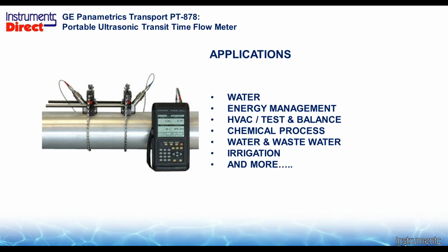Well, an ultrasonic transit time flow meter, as opposed to an ultrasonic Doppler flow meter, can be confusing. A Doppler flow meter basically works like police radar, sending a sound beam that bounces off your car and sends a signal back. A Doppler flow meter sends a sound beam and bounces off turbulence or chunks of stuff in the process liquid. Doppler flow meters will not work on a clean liquid application.